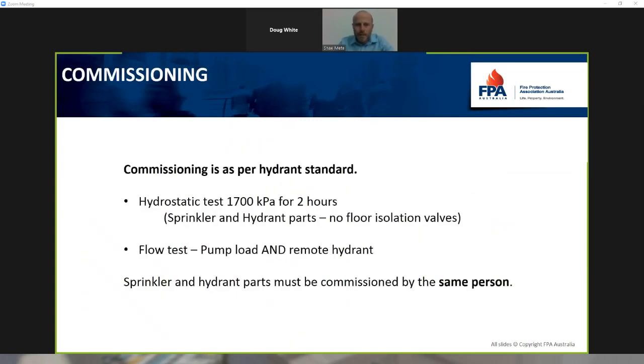Commissioning is exactly the same as required for the sprinkler and hydrant parts of the system as per 2419 and 2018. Hydrostatic test for up to 1700 kPa to be held for 2 hours, and a full pump test, pump load test, and a remote hydrant flow test as well. We do make the point that because these systems are combined, it is important that the same person conducts the commissioning of the system. We're worried that we might have, for example, the plumbers doing the commissioning on the hydrants and the sprinkler companies doing the sprinklers, and no one really communicates, and we might not achieve the right demands.